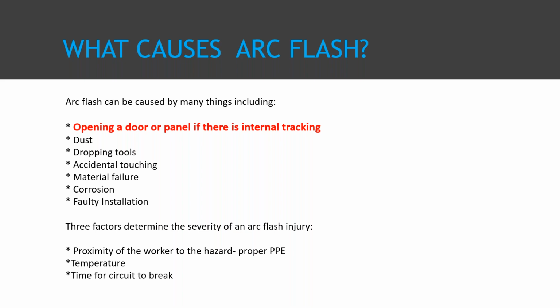Other things that can cause it, of course, dust, people working inside of a cabinet, dropping a tool, accidentally touching something, material failure, corrosion, you know, bad installation in the first place. All those things can happen, but one of the largest causes of it really is just opening that panel or that door without any kind of a pre-inspection. So there's really three different things that are going to determine how bad that arc flash injury is. One is how close you are to the actual arc flash, and are you wearing the proper PPE. So I would say, for all those who are required to work around electrical assets, don't skimp. No matter how short a period of time you're going to be exposed to those assets, it's a good idea to be fully decked out in the proper PPE.